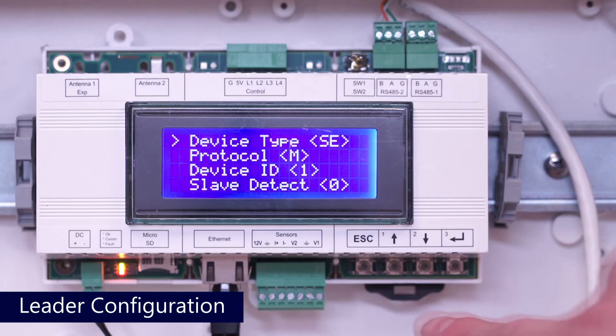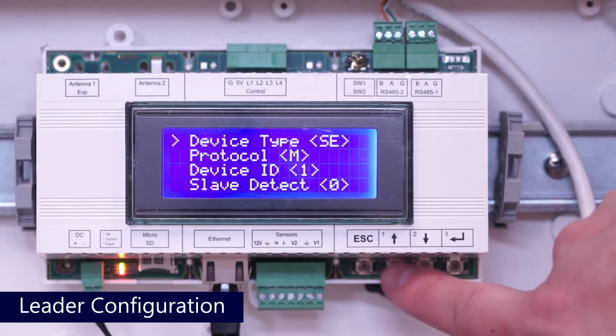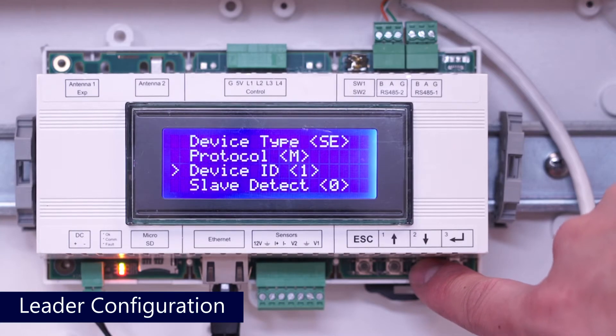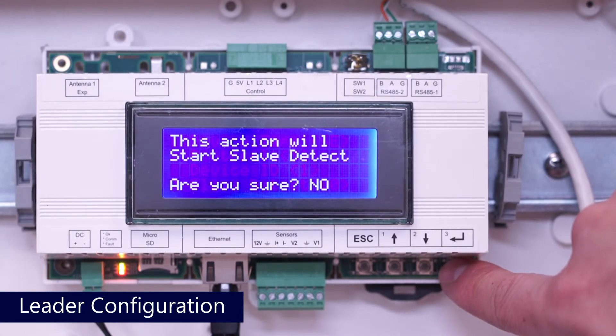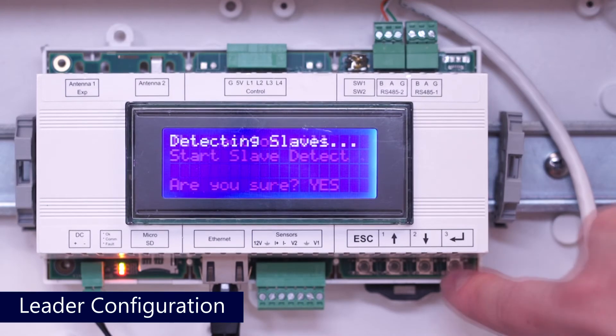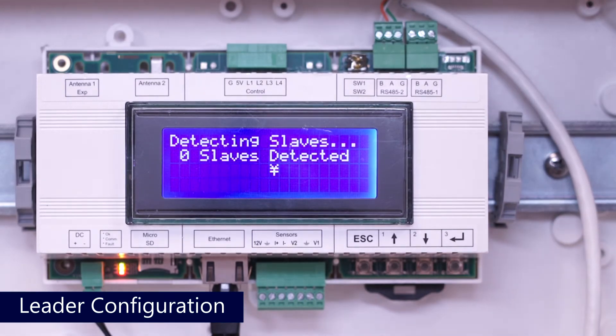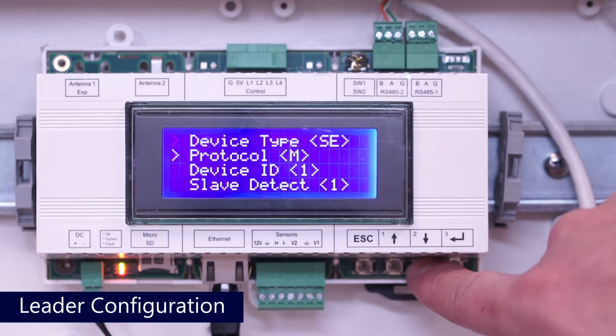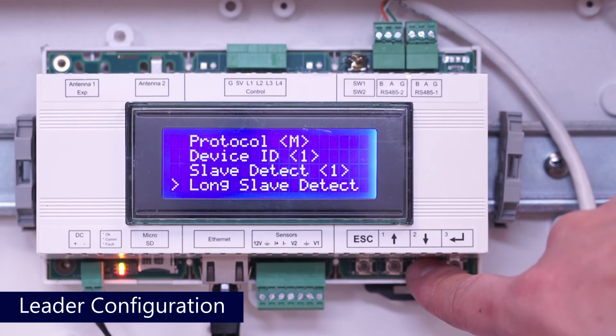Once set, scroll down to slave detect and press enter. Change the no to a yes using either arrow button and press enter. The gateway will now look for inverters connected to it on the RS485 bus. Once connection is complete, scroll to the slave list to verify serial numbers of the inverters connected to the gateway.